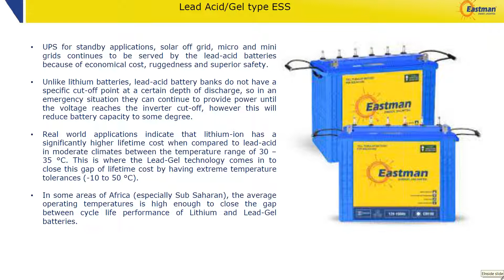It's basically its USP. Real world applications indicate that lithium ion has a significantly higher lifetime cost compared to lead acid in moderate climates, between temperature ranges of up to 30 to 35 degrees centigrade. This is where lead gel technology comes in to close the gap in lifetime cost by having extreme temperature tolerance. Lead gel is a proven technology, installed in the deserts of the Sahara in countries like Burkina Faso and Mali, and it has worked perfectly in sub-zero temperatures in Canadian off-grid power projects.